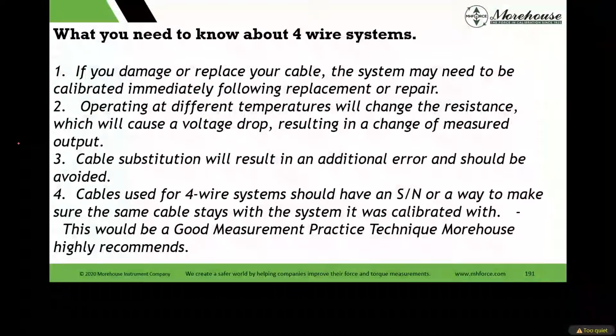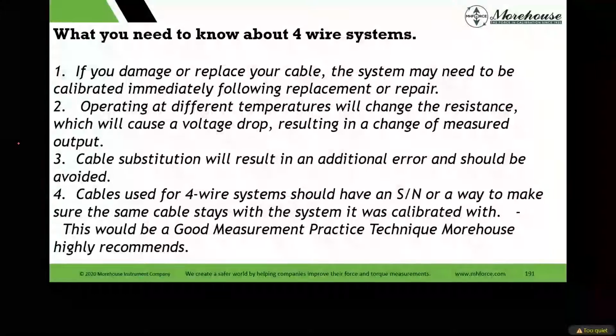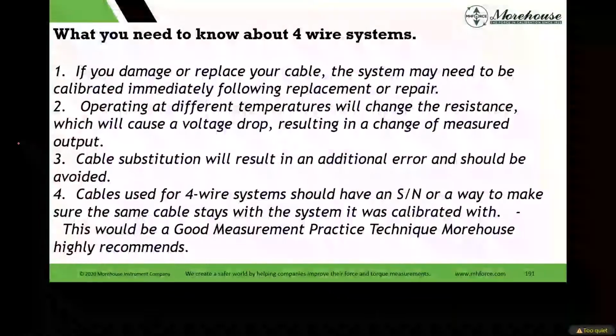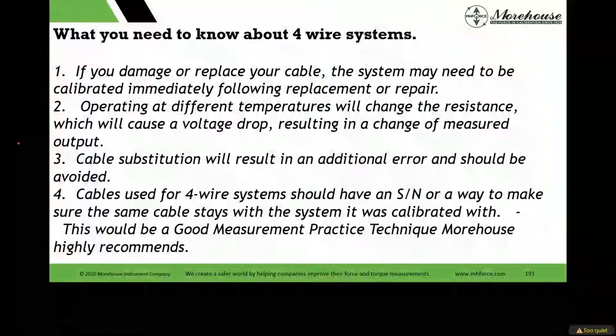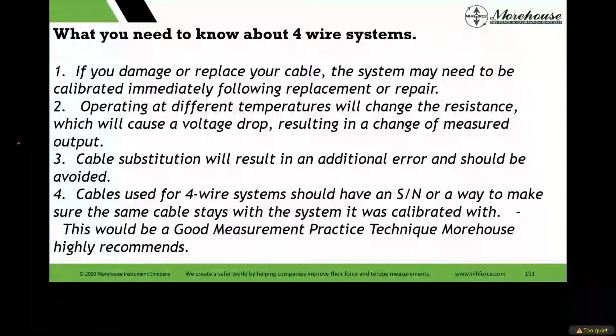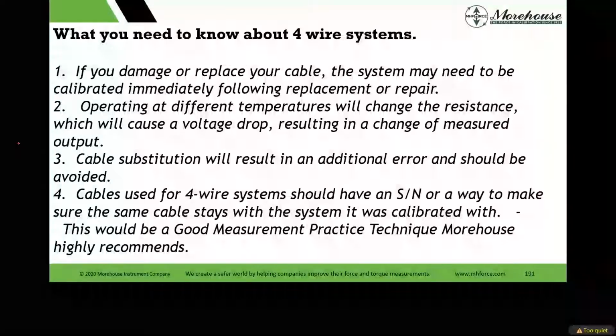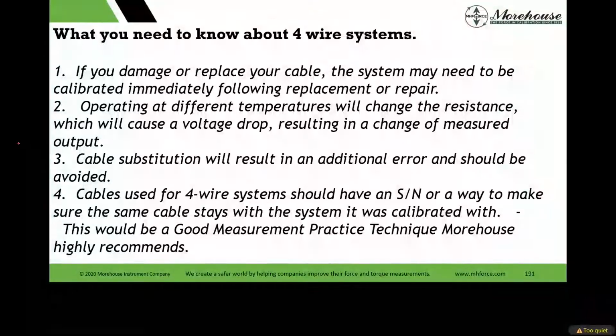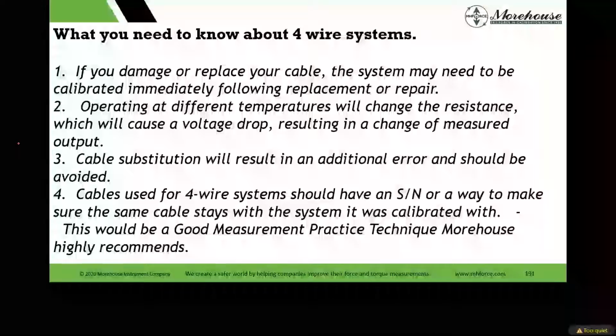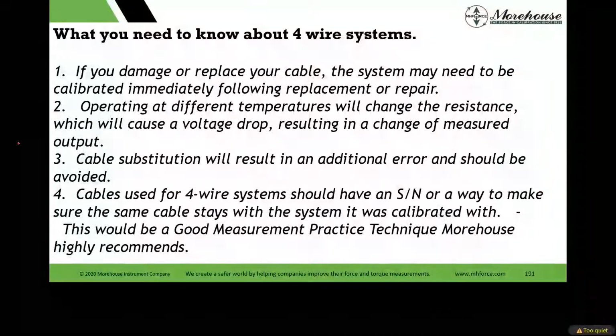Some recommendations. There are a lot of 4-wire systems out there that people like. ADMET Gauge Buster, which we have our own Morehouse Gauge Buster. It's ADMET rebranded because people like the smaller form factor, and we make no qualms or hide that at all. It's a good device. It's a 4-wire device. What you see happening is people like this because you can program multiple points. You have a freeze cable if you're doing machines. So your testing machine reads 2000, you put the freeze cable, you record what it means. Get it.